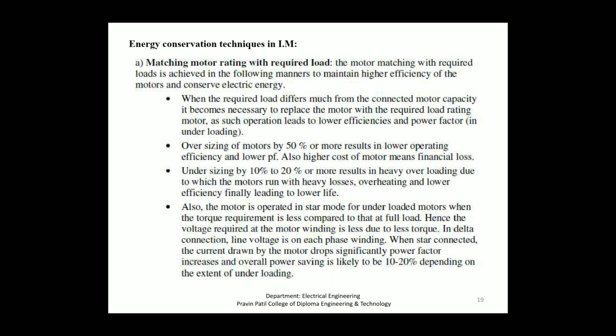Such operation leads to lower efficiency and power factor in underloading. Oversizing of motors by 50% or more results in lower operating efficiency and lower power factor. Also, the higher cost of the motor means financial loss. Undersizing by 10% to 20% or more results in heavy overloading, due to which the motors run with heavy losses, overheating and lower efficiency, finally leading to lower life.